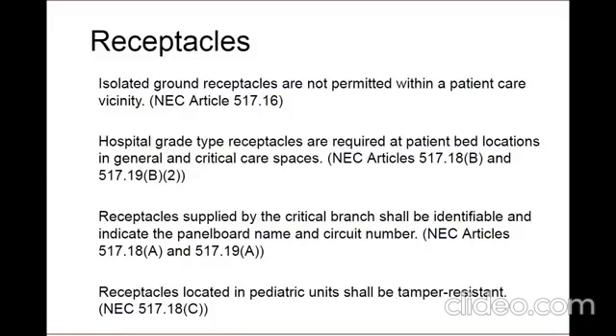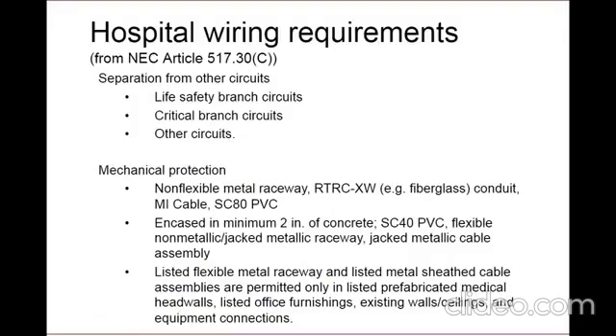The last special receptacle requirement I'm going to mention now is for pediatric wards. Receptacles installed in patient rooms, bathrooms, playrooms, and activity rooms in pediatric units must be listed tamper-resistant per NEC 517.18(C).